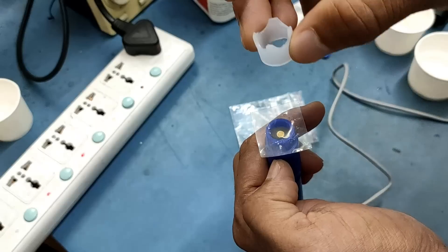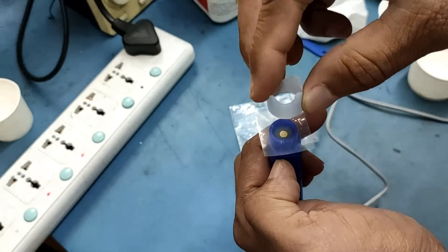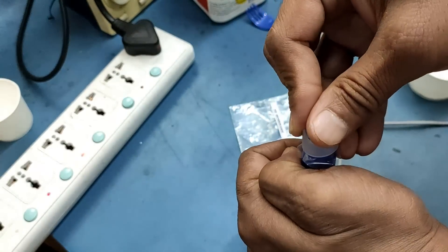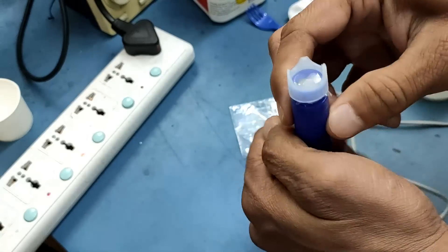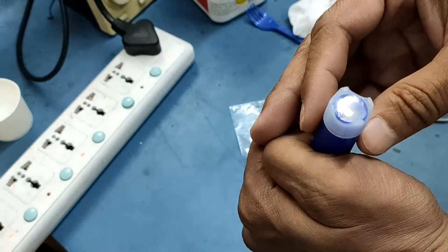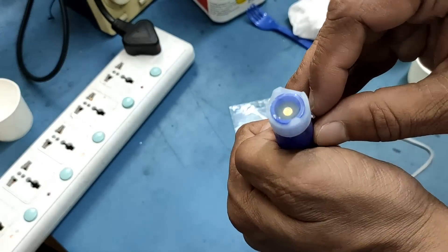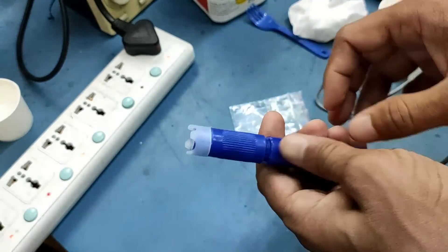Remove the membrane crown. Place the D.O. membrane on the cap and fix the crown to the electrolyte tube covering one side of the membrane. Make sure that there are no wrinkles in the membrane and that it does not get punctured or damaged.